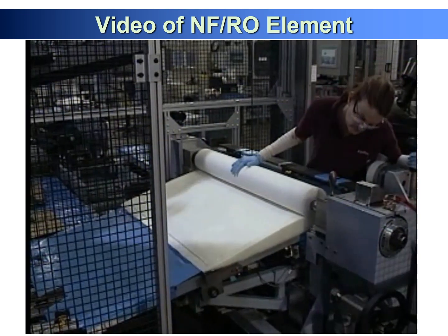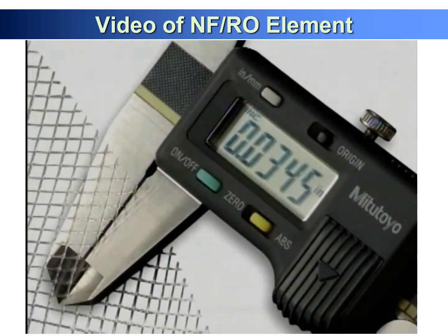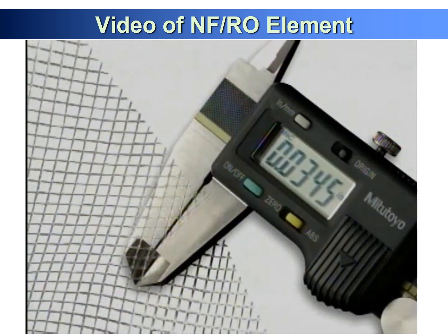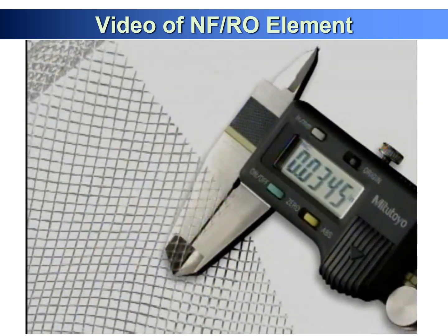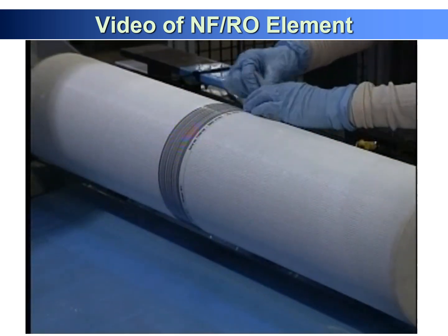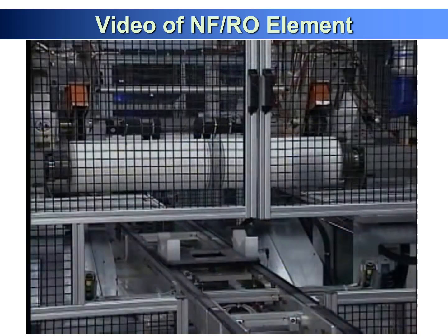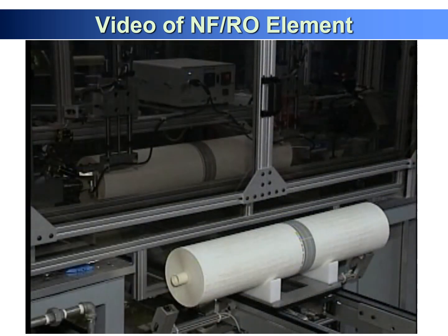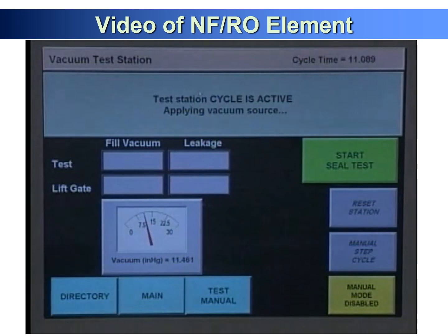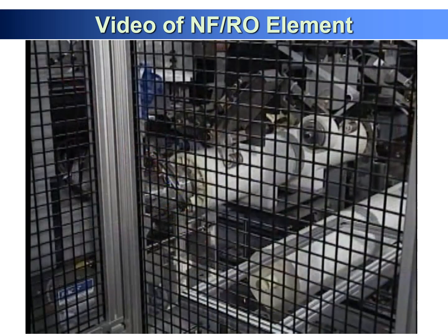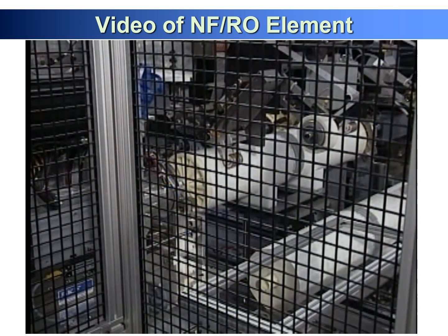FilmTec elements are optimized to have the highest active area combined with the thickest feed spacer in the industry, offering several operating benefits, including improved cleanability, lower pressure drop, increased durability, and the ability to handle more challenging feed waters. A unique barcode allows continuous tracking of each element. Online quality checks for scroll integrity and dimensions and an inline vacuum test are performed on every element to ensure mechanical integrity. Any elements failing preset measurements are discarded. End caps are welded to the product water tube in a process that improves element strength, and a quality test ensures weld integrity.